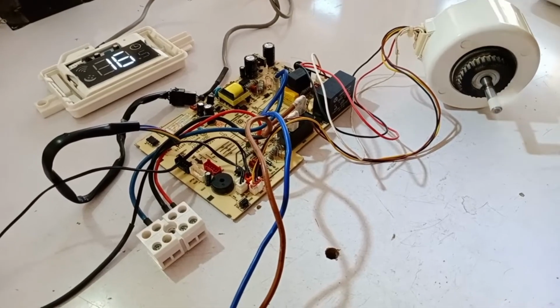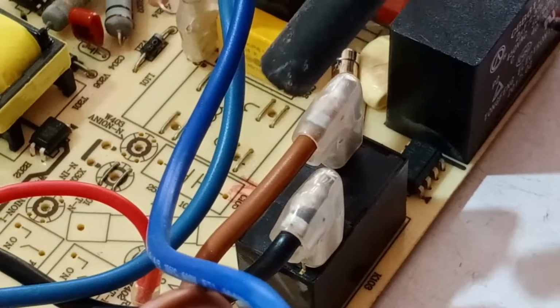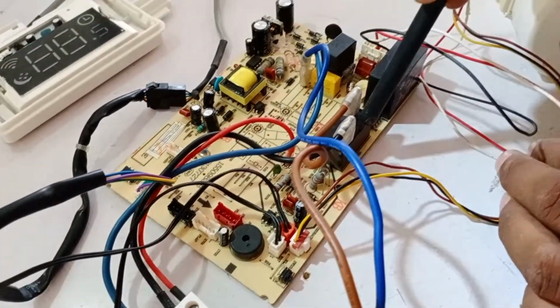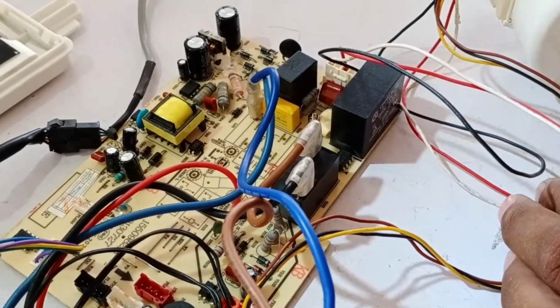2. Faulty switching relay. The relay is responsible for switching signals. Power is coming from one side and returning via the black wire. If the relay becomes faulty, it will also trigger error 36. You should check the relay, and if it is damaged, replace it.